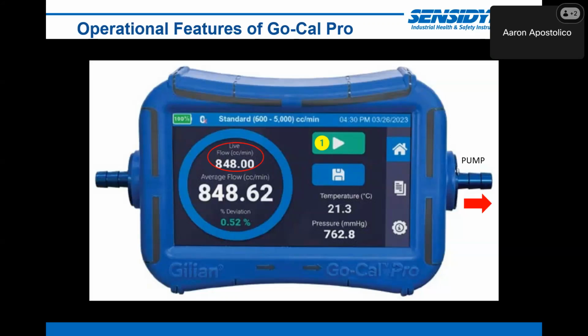So the other thing that you can do is you hit this play button and it'll actually sample for a set determined sampling time. And then you get an average flow for that sample period. You'll also get that percent deviation that I just spoke about. Once you have that, you have the option to now save your calibration event. And then of course you can view the calibration event in your reports tab within the instrument itself.